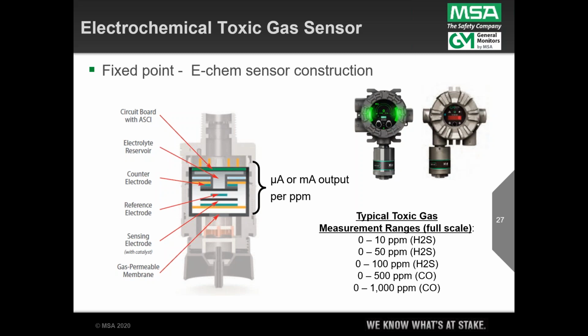And then the transmitter module converts that to a milliamp signal and usually has a local onboard display as shown in the upper right. But then also we would route that signal to a logic solver, a gas controller, to provide audio visual alarms and then some notification. And obviously we want to also log that data. We want to be aware of how often we're having alarms, that kind of thing. So that's a brief rundown on electrochemical gas sensors.